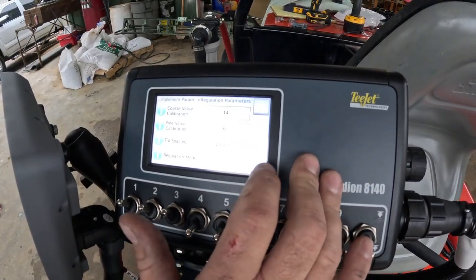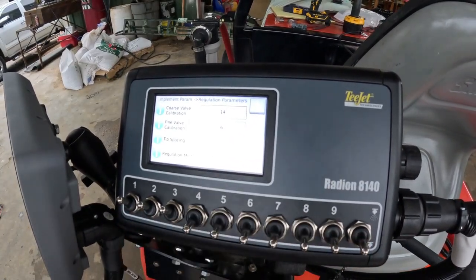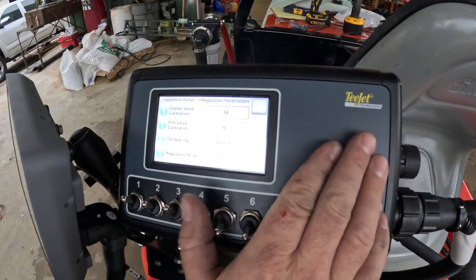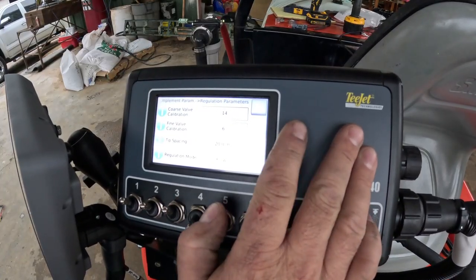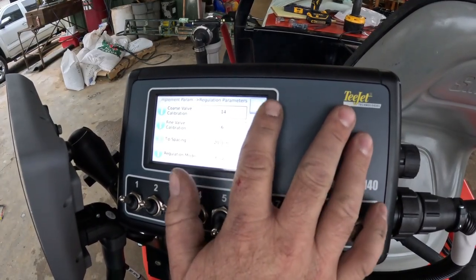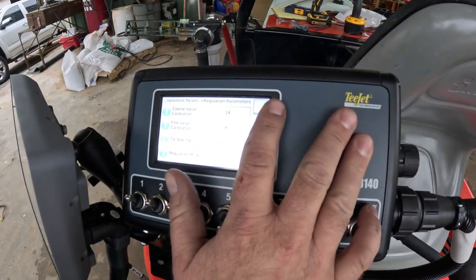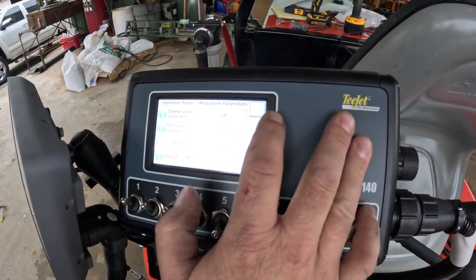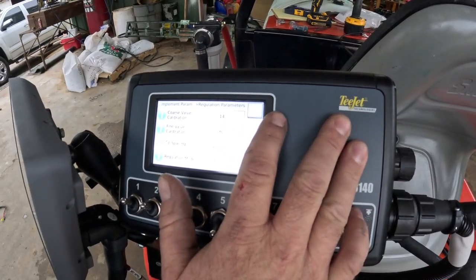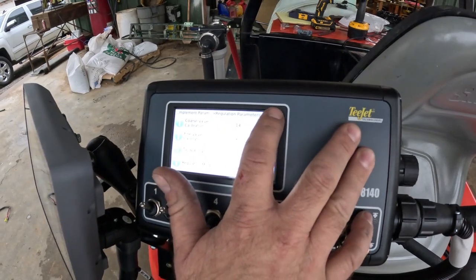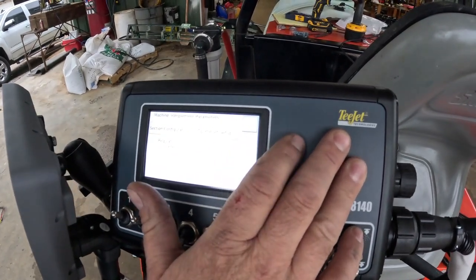Your regulation mode is in flow mode, so that means that this controller is always going to operate using the flow meter that's on here. And the flow meter that's on here is the EM flow meter, so it's 0.6 to 100 gallons. So if you get down below 0.6 gallons per minute, it will change itself over automatically to pressure-based application. So we're going to go back. Now we're going to go into calibrations.